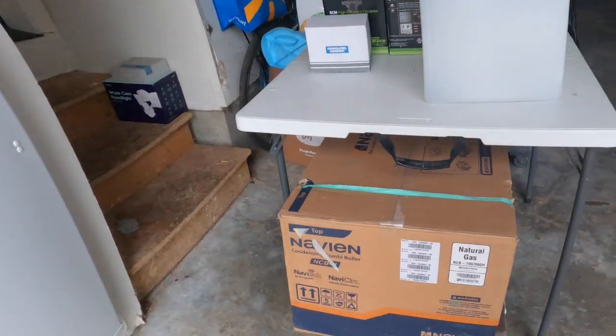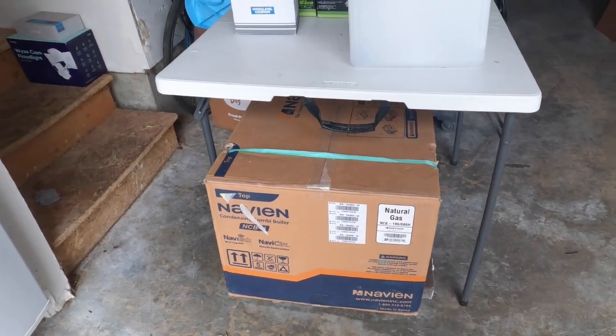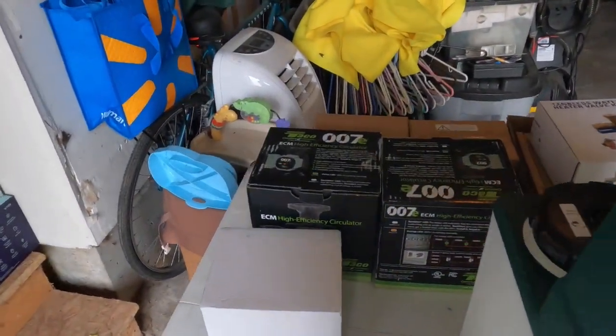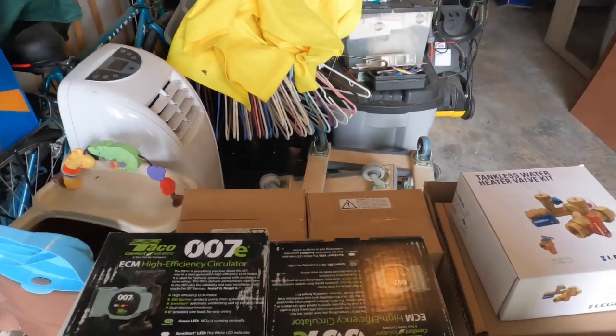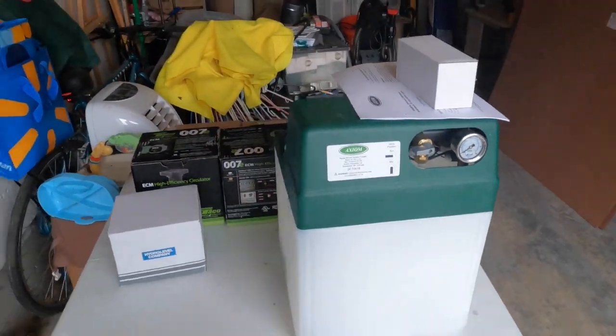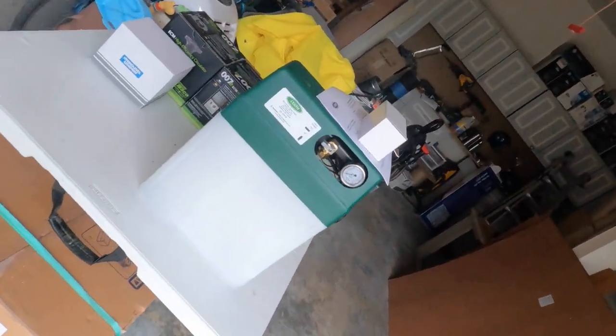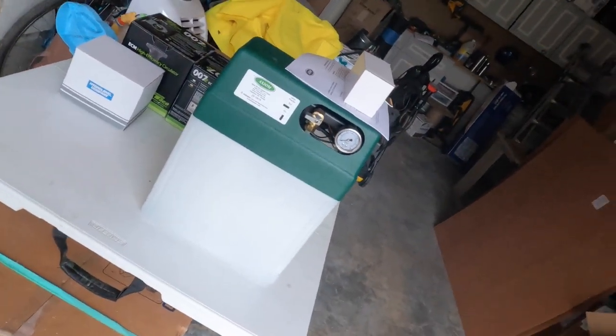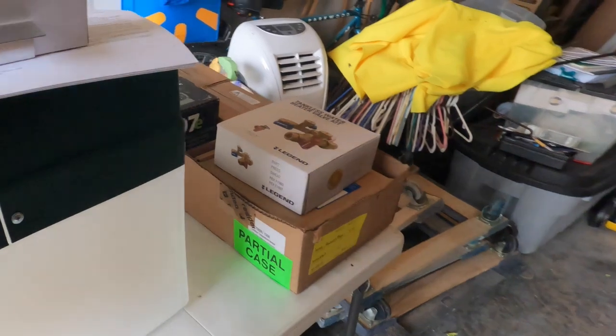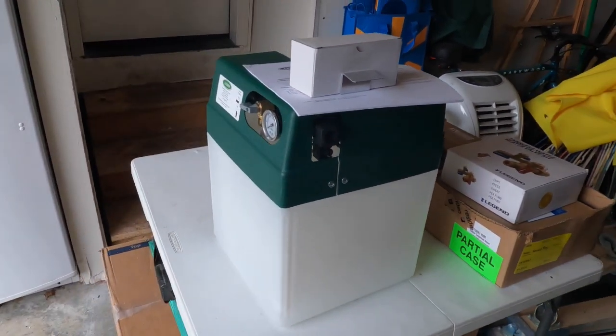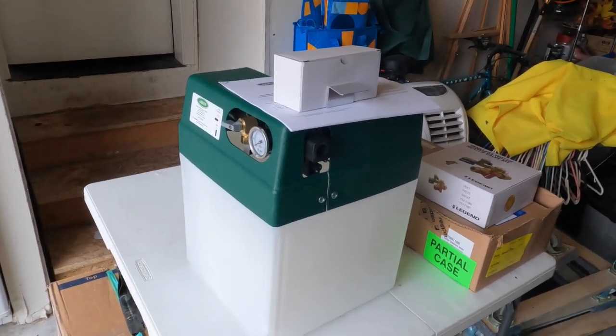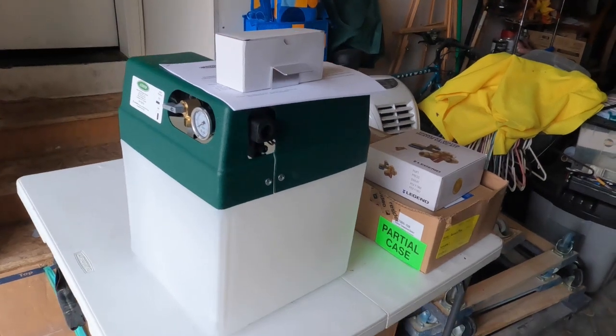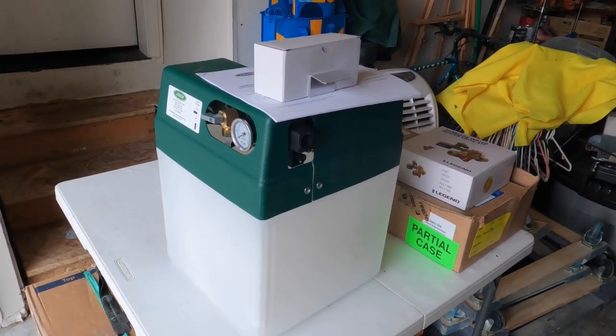So this is the continuation to the boiler epic inspection failure that we put out last week. What we have here is a new Navien condensing combi boiler, a couple of new circulators, some isolation flanges, some isolation valves, and a relatively new product, the Axiom Pressure Pal. What this does is we fill this with water and connect it to the heating system, and it not only provides the fill, but it also pressurizes the system to our desired pressure. Kind of nice, that way there is no connection to the domestic water system.